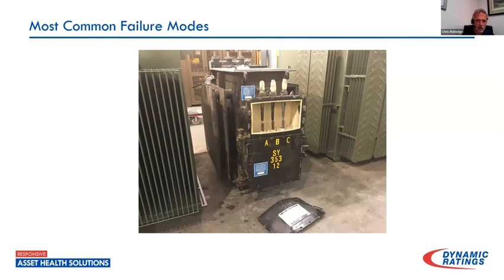Monitoring of the main tank is not a costly piece of equipment. If I place hydrogen monitoring in the main tank, I'll see things like partial discharge and thermal overload of the main tank cores and coils. However, there's no indication whatsoever of what's going on inside the cable compartment. To effectively do this, I'm now looking at monitoring for all three compartments. Going with the lowest cost option — hydrogen monitoring — that's several thousands of dollars to do that.